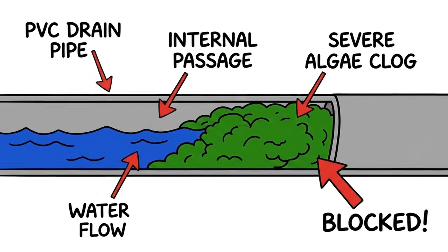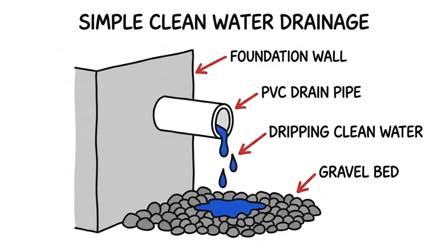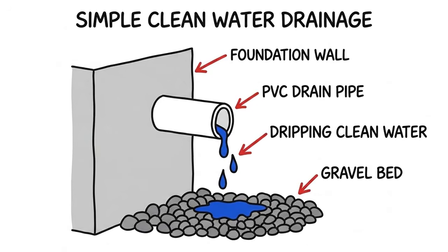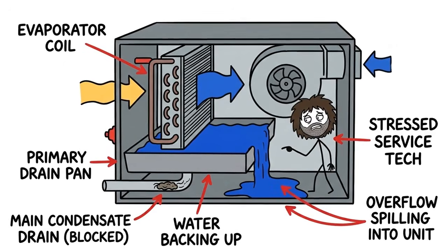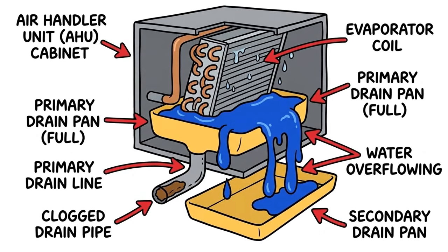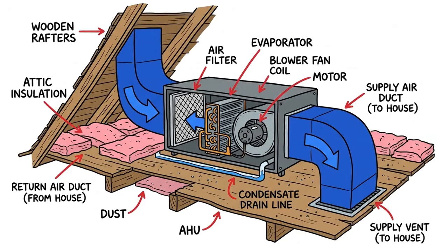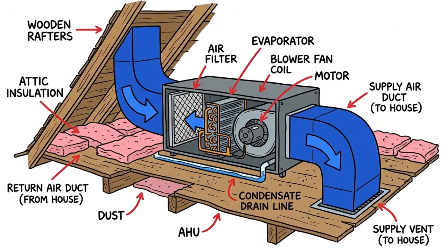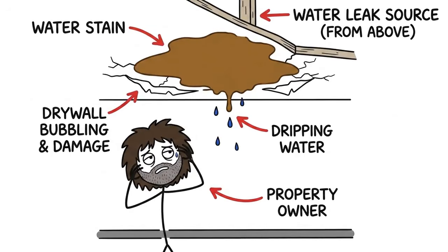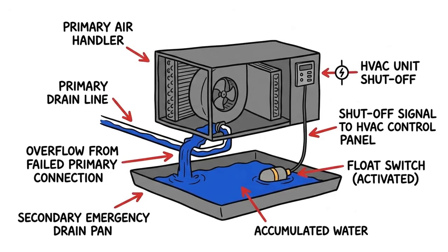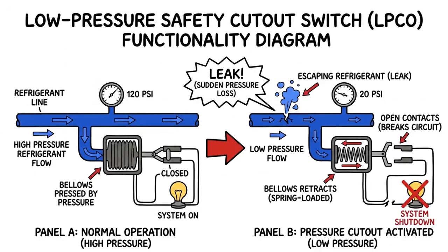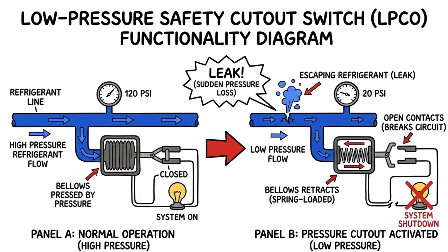The primary purpose of your HVAC air filter is not to clean the air you breathe. It is to protect the evaporator coil from dust. Aluminum evaporator coil fins are spaced mere millimeters apart. Dust buildup acts like a blanket, blocking thermal transfer. If dust coats the evaporator coil fins, air cannot touch the cold copper tubes, and your system loses cooling capacity rapidly. Even worse, restricted airflow across a 35-degree evaporator coil causes the coil temperature to drop below freezing.